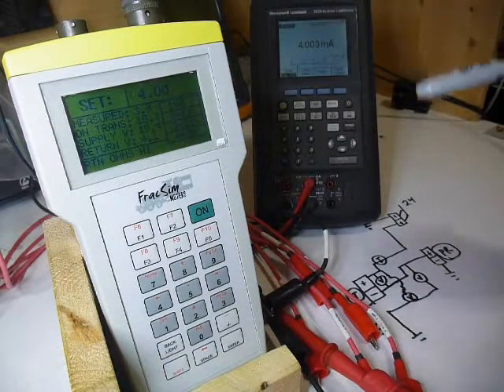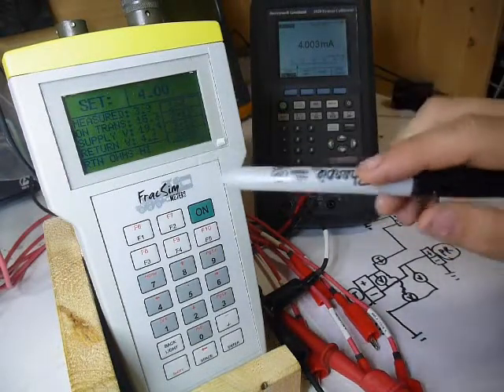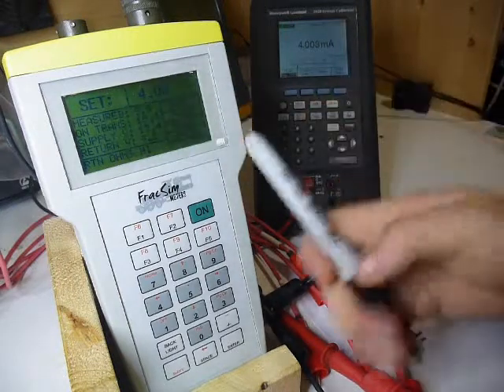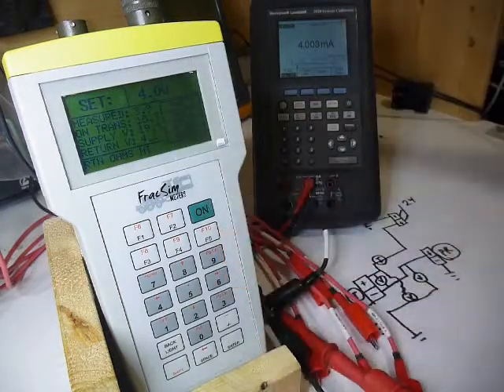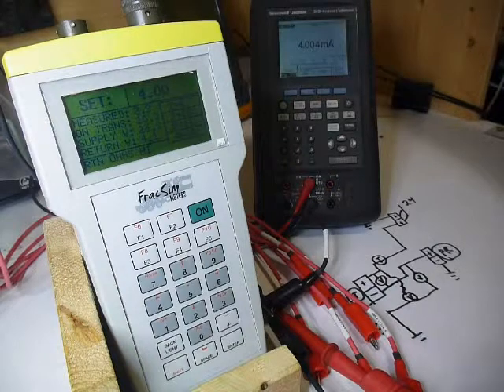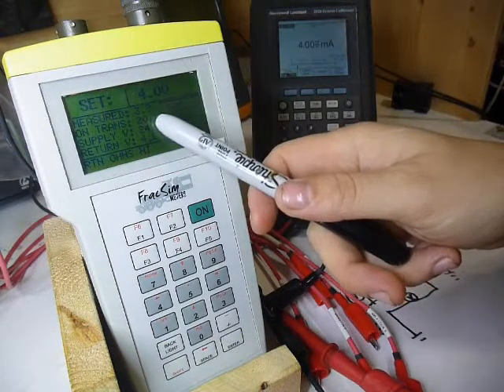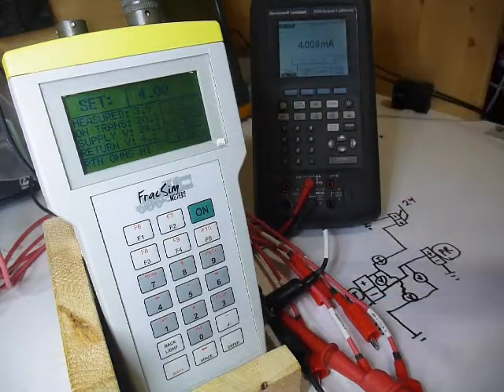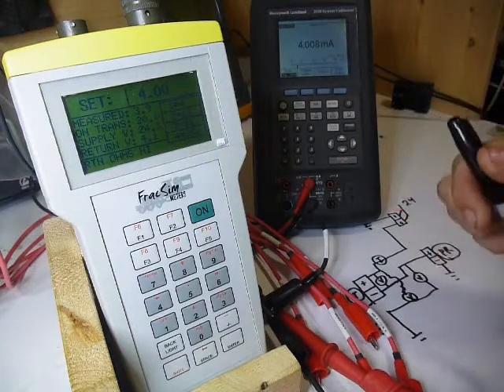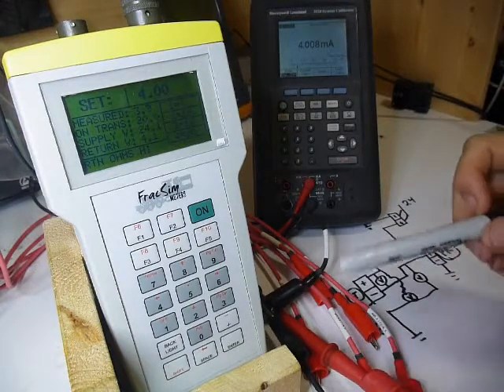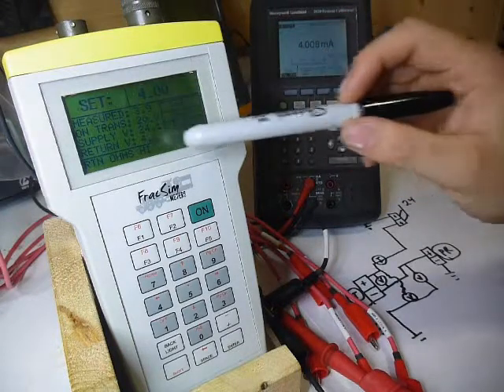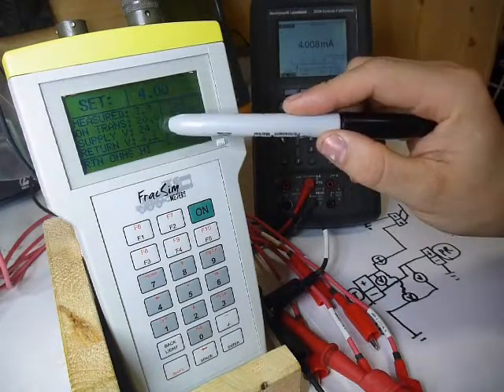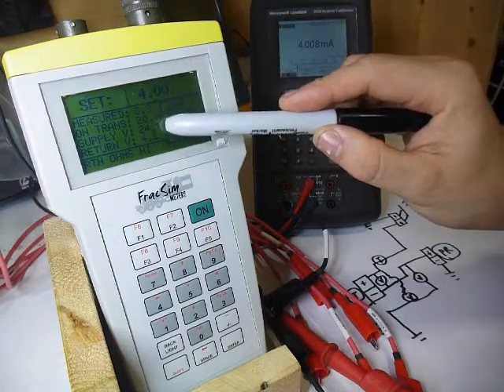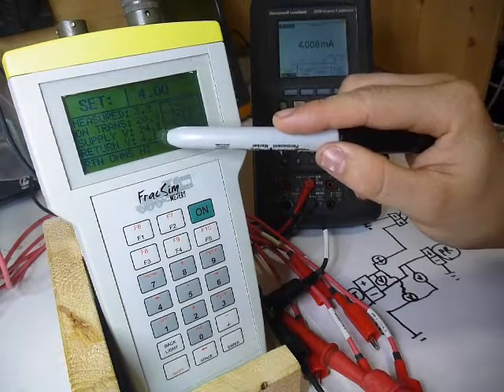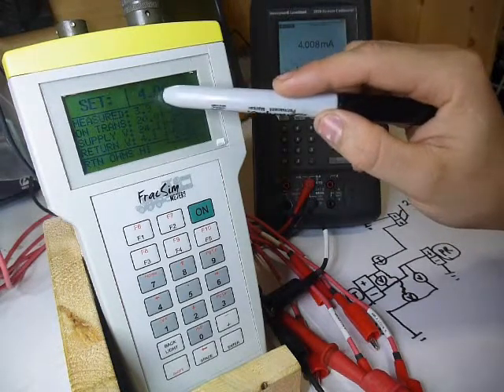So we have a resistance on the low side, and you can tell just because the supply voltage is still, I'm going to put my supply up to 24. So our supply is still 24 volts. So if we had this fault on a unit, a 1000 ohm load somewhere, you can tell it's in the return side by looking at these measurements. So we got 24 volt supply, so we know that the supply voltage is good, but our return is at 4 volts, and we're only pushing 4 milliamps.